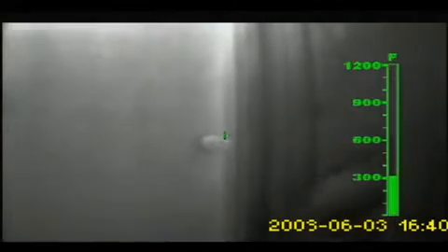When it was deployed, we closed the door on it. After that, there was a loud hissing sound — it sounded like water or some type of suppressant being applied to the room, real loud out there. After about 20 seconds, we opened the door — immediate blackness. There was no involved fire, no fire meeting us at the door. Immediate thermal readings of the room had dropped by half: ceiling was 600, the floor was right around 300 degrees.